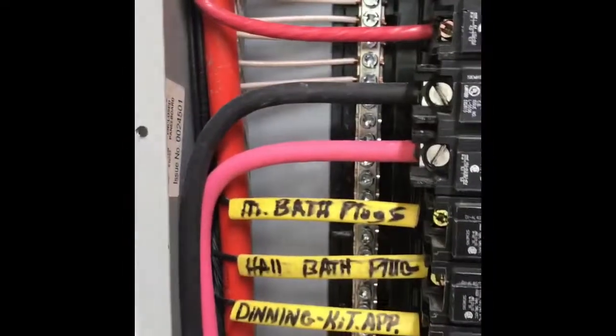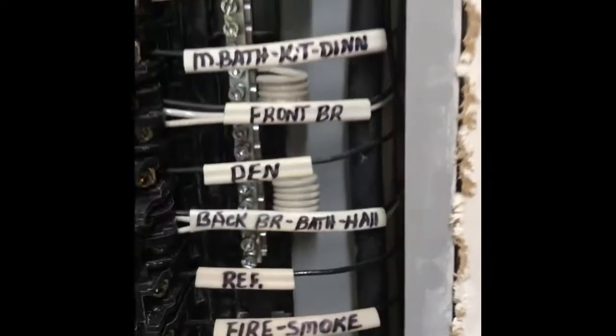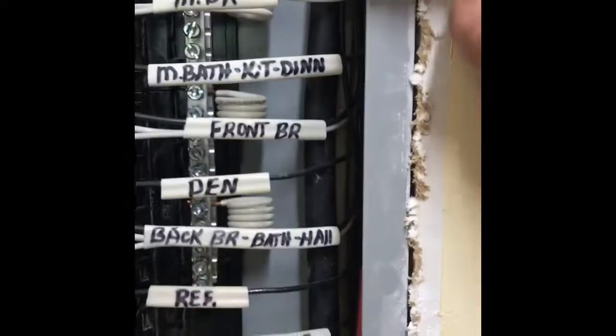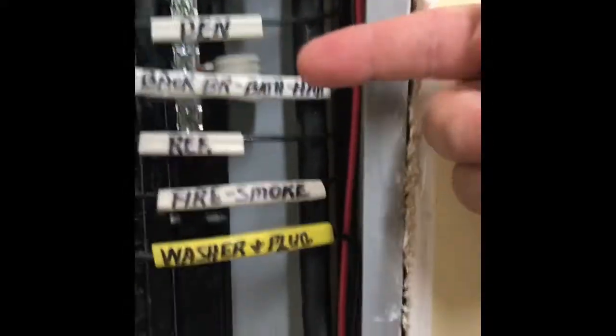This panel's clean. They used all the proper bushings for all the penetrations. They've actually gone one step above and labeled, when you take the panel face off, the labels are on there. But when you're trying to look and see what circuit goes to what, it gets confusing. You've got to keep looking back and forth. Well, they were nice enough. They went ahead and labeled everything within the panel what it is.